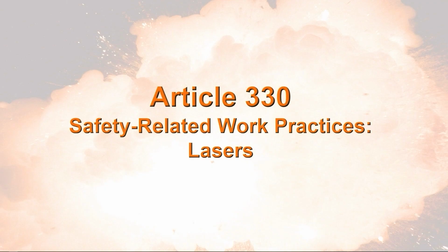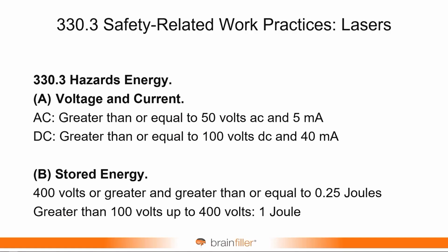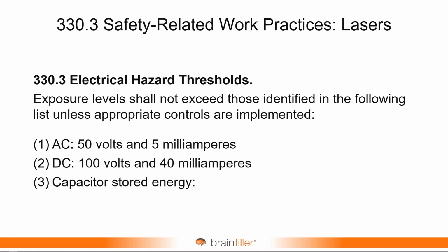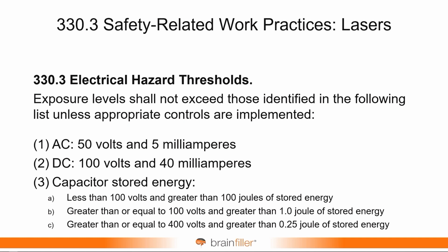Safety-related work practices for lasers, Article 330. Same kind of a thing here. The hazardous energy, this was modified. In fact, what happened is the hazardous energy for capacitors was greatly enhanced. Less than 100 volts and greater than 100 joules. As long as those values are not exceeded, you're good. If those values are exceeded, you have to have appropriate controls in place. Greater than 100 volts and greater than 1 joule, as long as you don't exceed those, you're good. Once you exceed them, you're not. And then the last one, greater than or equal to 400 volts and greater than 0.25, that's another electrical hazard threshold that if you exceed it, you have to have appropriate controls in place.